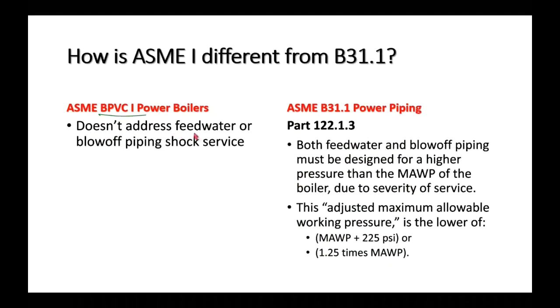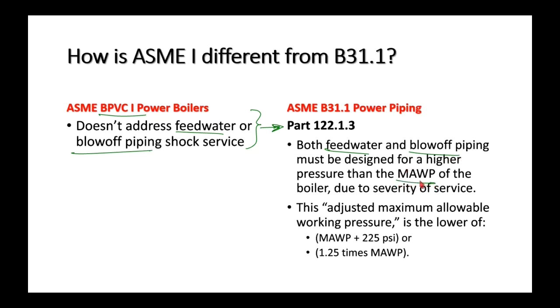You might think there should be something in the ASME code about feed water and blow-off piping — there used to be, but in the early 1970s it was moved over to the B31.1 Power Piping Code. The power piping code says feed water piping and blow-off piping must be designed to a higher maximum allowable working pressure than the actual boiler, because it's severe service — also called shock service.